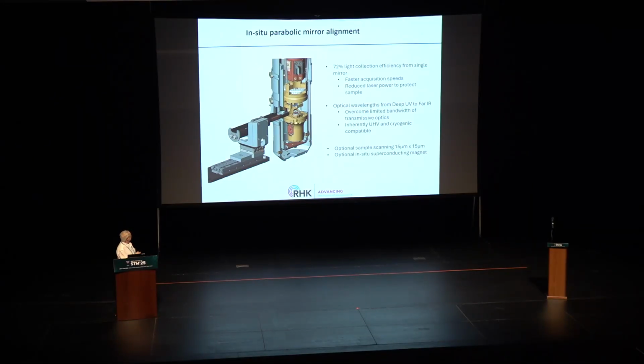An important thing about having such a high collection efficiency is, one, you can just go a whole lot faster. Sitting at every point, integrating data in a spectrometer can burn up a lot of time. But also, without this, you're going in with quite high laser power, which can bleach out your sample and damage it. Since you have such a high collection efficiency, you can really turn down the power of your laser. Also, being reflective optics, it has very wide bandwidth, so you can work from UV to IR without having to change anything inside of the chamber.